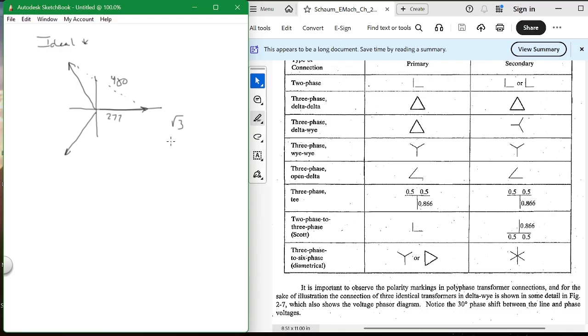You measure voltage phase to phase as 480, and phase to ground as 277. The relationship is the square root of 3. You can also find this in other flavors, this would be half of that, 240.